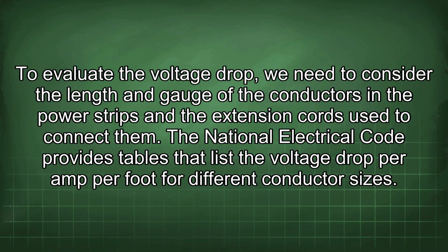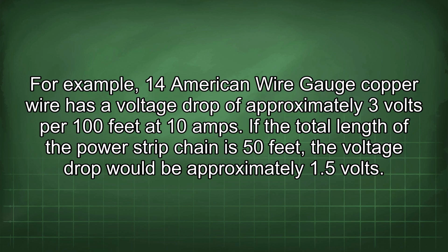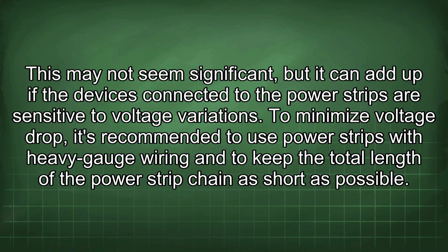To evaluate the voltage drop, we need to consider the length and gauge of the conductors in the power strips and the extension cords used to connect them. The National Electrical Code provides tables that list the voltage drop per amp per foot for different conductor sizes. For example, 14 American wire gauge copper wire has a voltage drop of approximately 3 volts per 100 feet at 10 amps. If the total length of the power strip chain is 50 feet, the voltage drop would be approximately 1.5 volts. This may not seem significant, but it can add up if the devices connected to the power strips are sensitive to voltage variations.